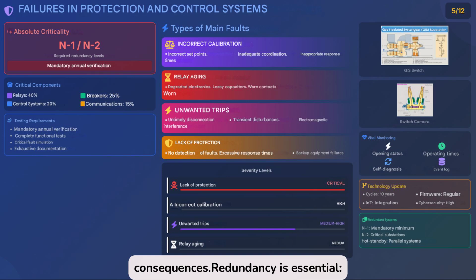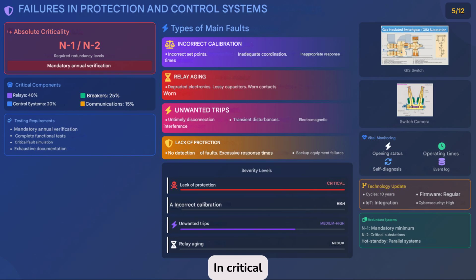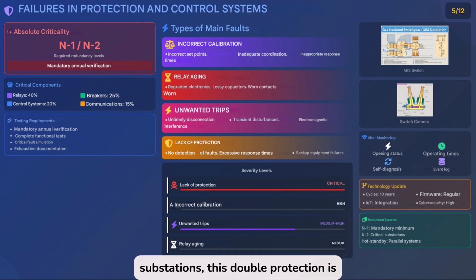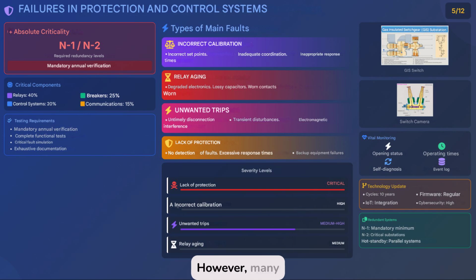Redundancy is essential. The N-1 and N-2 configurations ensure that even if one component fails, another can take over. In critical substations, this double protection is mandatory. However, many installations fail to comply with annual verification, increasing operational and financial risks.